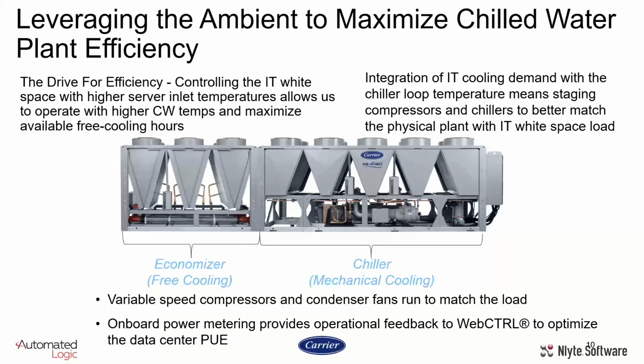We have variable speed compressors and variable speed condenser fans, which can be run better to match the chiller capacity with the load. And we have onboard power monitoring, providing real-time operational feedback to web control to optimize the data center PUE. Next slide, please.